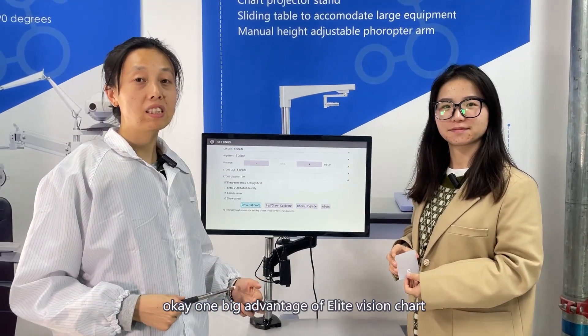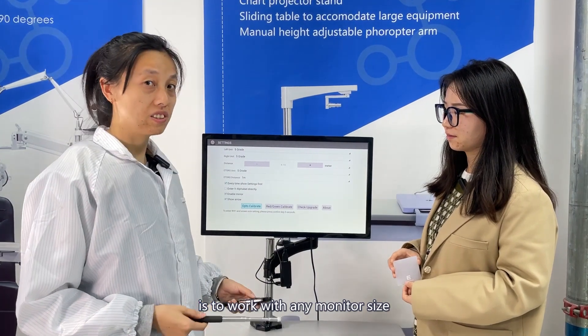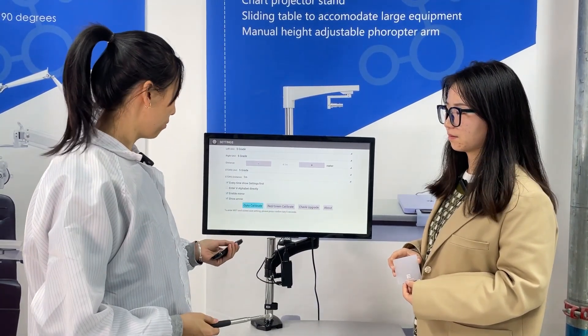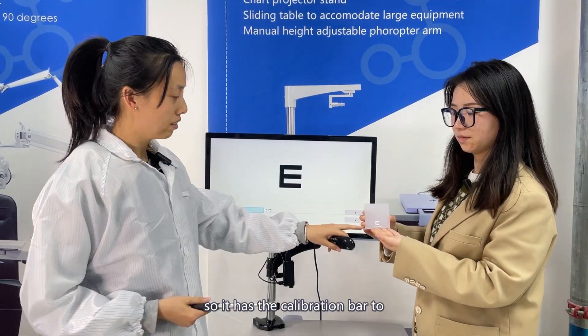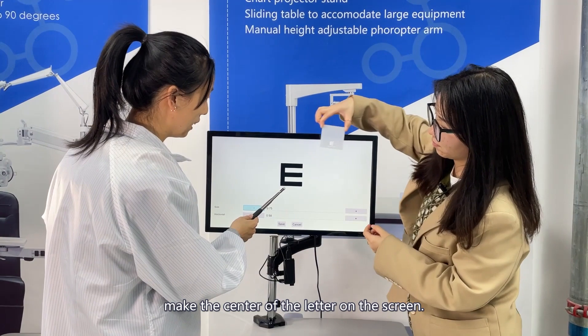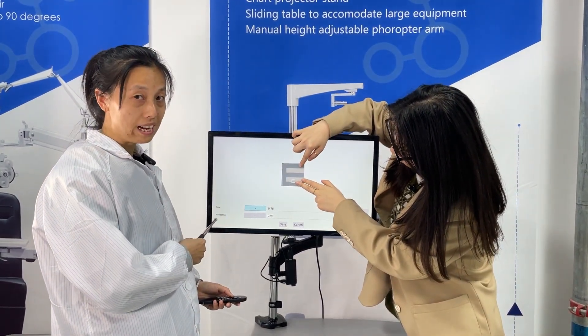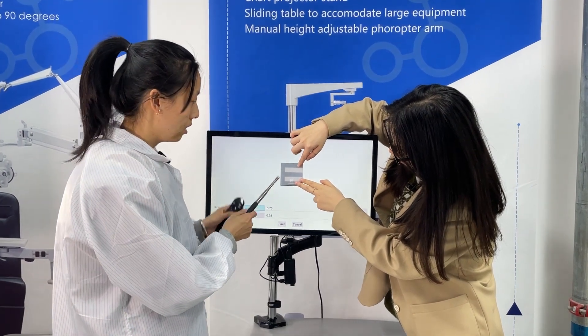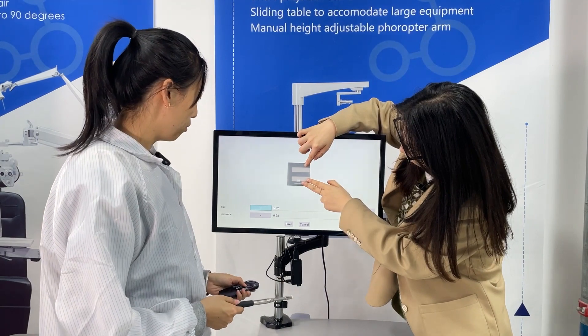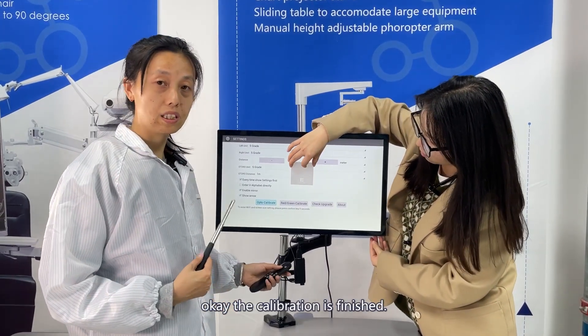One big advantage of Elite Vision Chart is to work with any monitor size using the auto-calibrate function. It has a calibration bar — center the letter E on the screen, then adjust the size and horizontal size to match the calibration bar, and save. The calibration is finished.